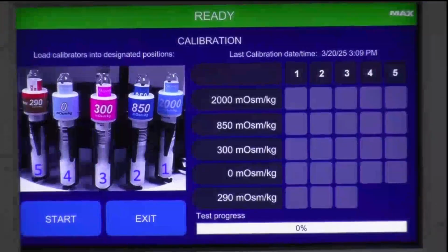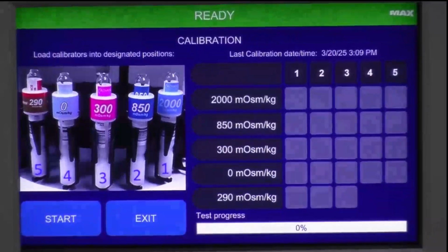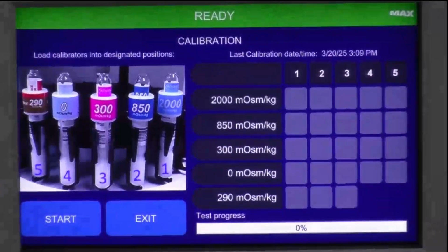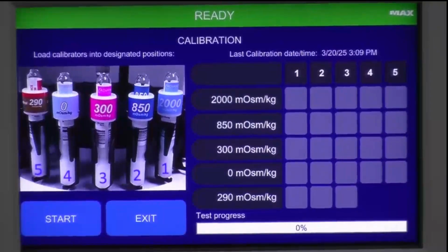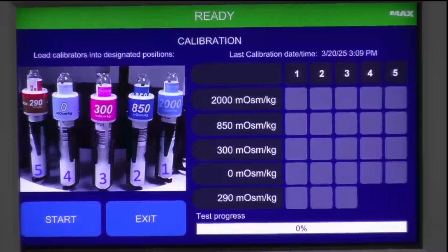And then we're going to go back to the screen here. It's going to say ready. It wants me to start my calibration. So over on the left, you're going to see exactly how you need to position those ampule adapters and the ampules that coordinate to each ampule adapter, starting from the highest level at 2000, descending down to 0, and then the 290. We're going to start running this calibration. I'm not going to do it right now.